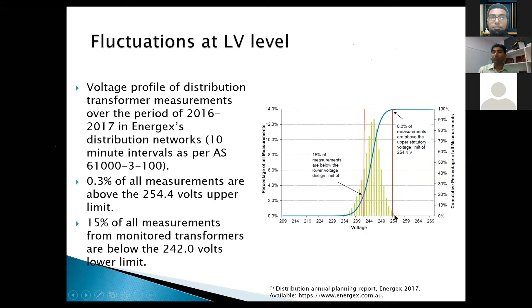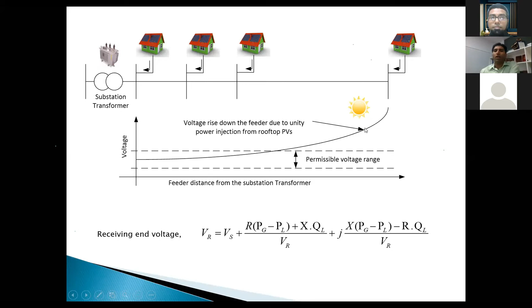So essentially the idea, as I told you, is that farther down the line — this is all power engineers know — there's a typical formula for calculating the receiving end voltage when you have a stiff sending end voltage and injection from the given feeder. You can see that the farther away you are, the higher the voltage will be.